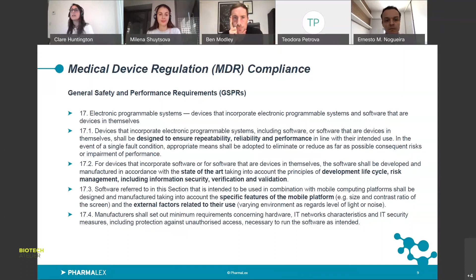One new section is section 17, which talks about electronic programmable systems. So you need to be able to demonstrate that your product is designed to ensure repeatability, reliability, and performance, that you've considered the state of the art and you're taking into account the principles of development lifecycle, risk management, including information security, verification, and validation. And in the case of a mobile device, you need to think about the specific features of that platform, such as the size, any limitations that might introduce, or any external factors related to their use, such as which environments is it going to be used in. So these all need to be considered and addressed within the GSPR checklist.